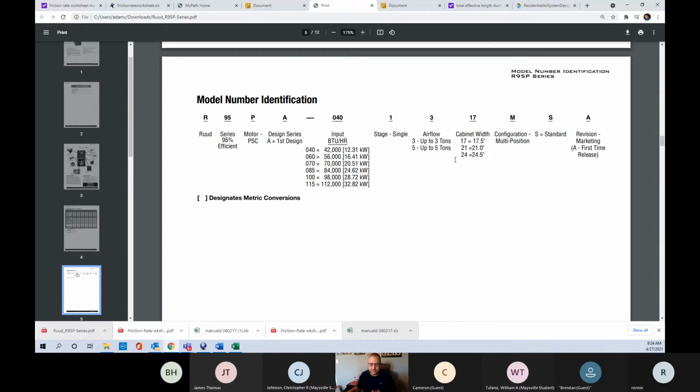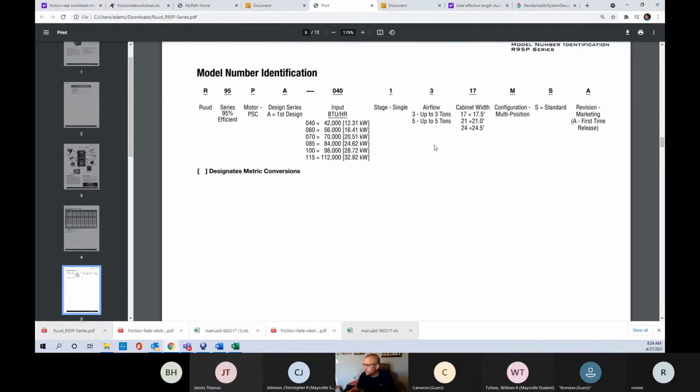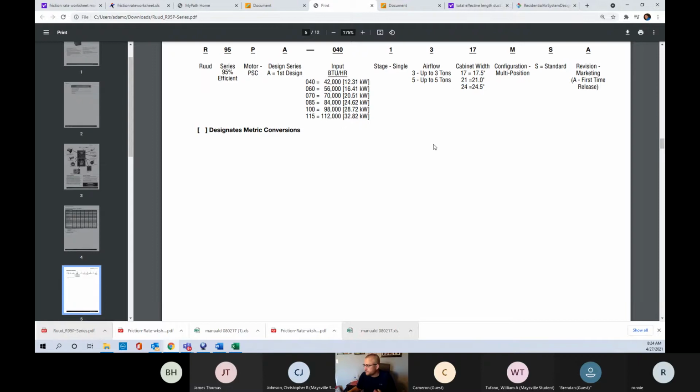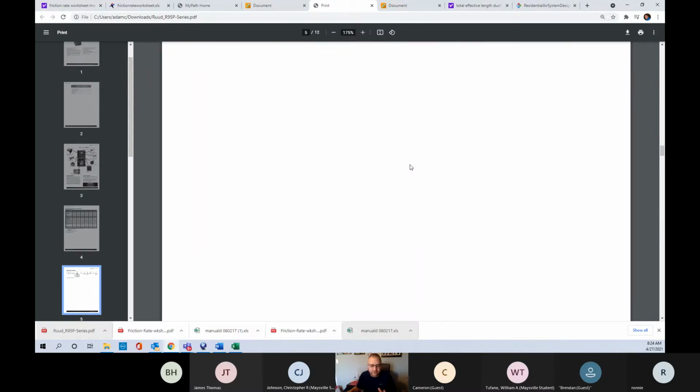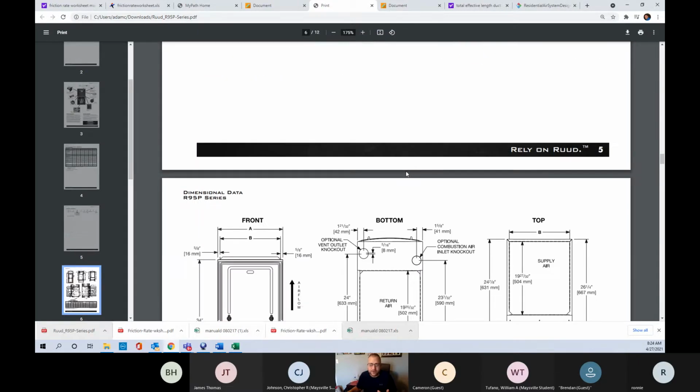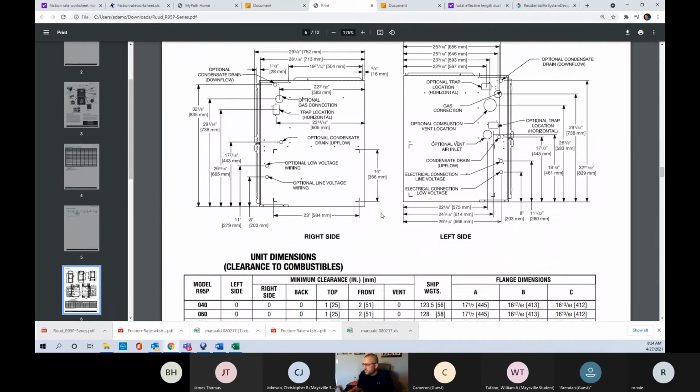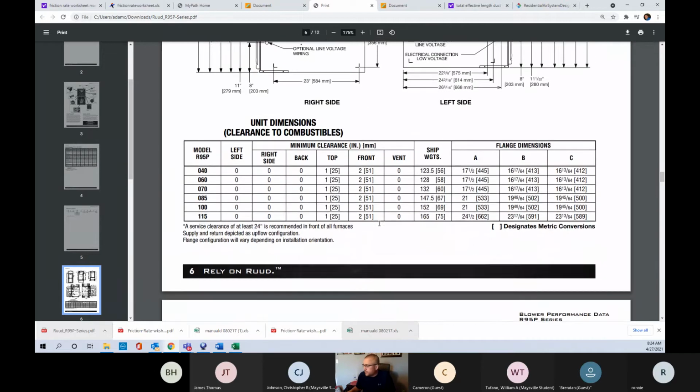And then you go in and actually set your speeds. So if it's a 90,000 BTU furnace or whatever, then you set it for your AC match and your heating output match. You can make this furnace work in a lot of different places. So you're not going to get a 3.5 ton furnace blower. You're going to move the speeds of that blower to get what you want. So they're a little more generic than what you'd think, maybe.